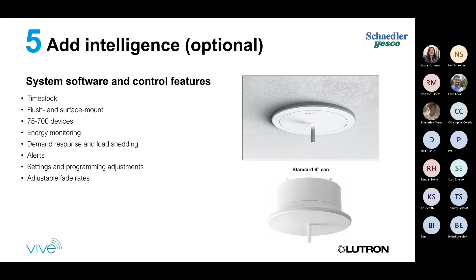Another nice feature is integration with third-party systems, such as a building management system. Through BACnet, we can send data like occupied or unoccupied status of a room, so on the mechanical side you can throttle back temperature controls based on whether the space is occupied.